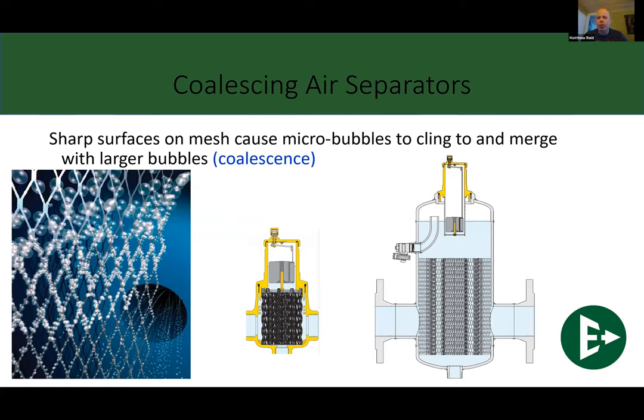A good example of what this looks like: if you take a water bottle and shake it, you'll see those bubbles come out of solution. That's kind of what it's doing. But in this case, the system is under pressure, and those bubbles that we create by creating this turbulence under pressure need some place to go. So with the coalescing media on the inside, be it whatever it is, it all sticks together. And as those bubbles stick together, they get larger and larger, and as they move to the top, eventually that's how they spit themselves out. Now, this is an extremely efficient way of getting air out of a system.